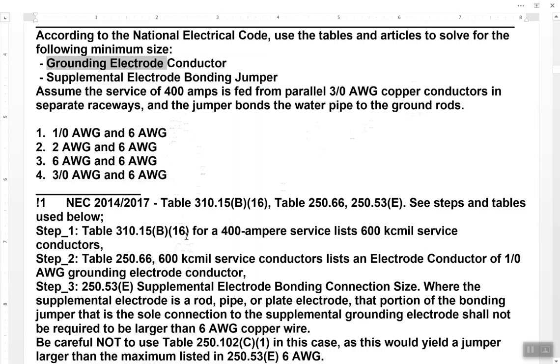So let's go to that table, okay? And let's look at what size my service conductors must be. Let's go and look at the ampacity here, right? Let's look at the ampacity 400 amps, and let's look it up here as to what size it would be, right? We know it's in parallel here, but in this case, to size it, we need to know the ampacity. Use this table to size it so we can take it on over to the grounding electrode conductor table and then size the grounding electrode conductor.